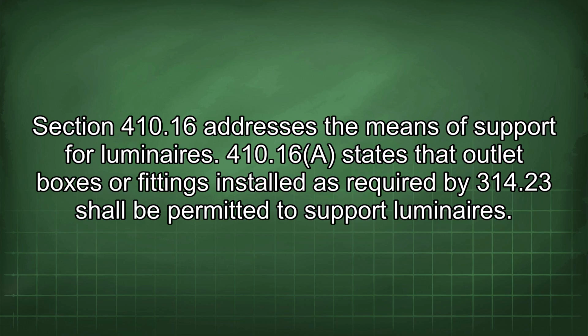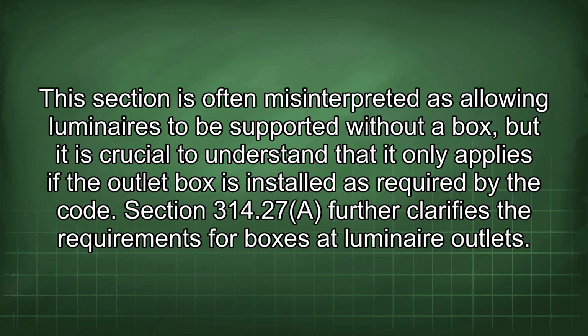410.16 states that outlet boxes or fittings installed as required by 314.23 shall be permitted to support luminaires. This section is often misinterpreted as allowing luminaires to be supported without a box, but it is crucial to understand that it only applies if the outlet box is installed as required by the code. Section 314.27 further clarifies the requirements for boxes at luminaire outlets.